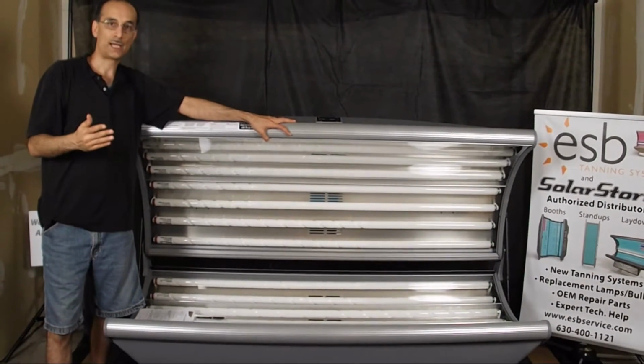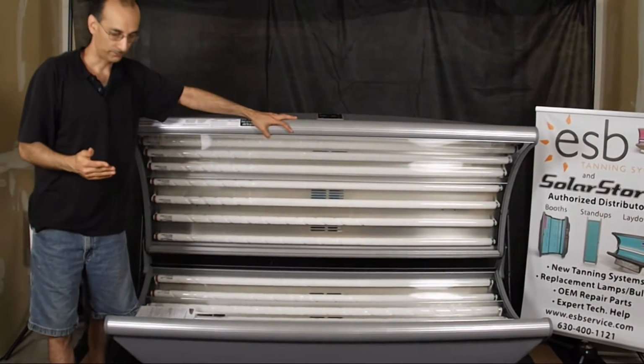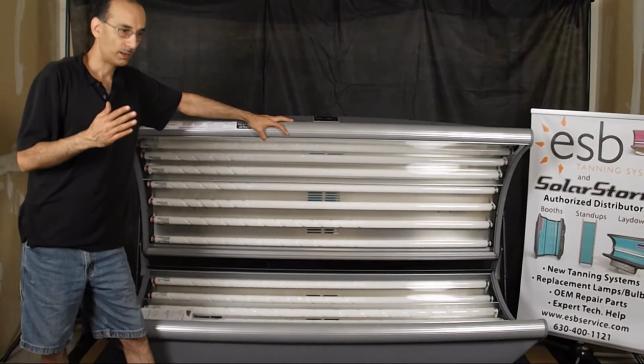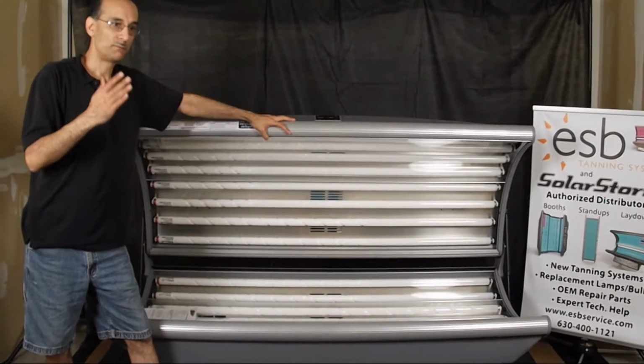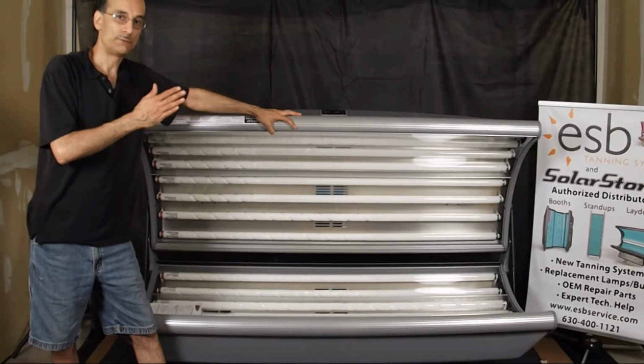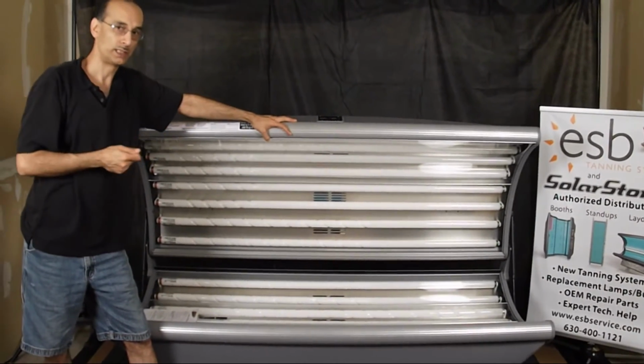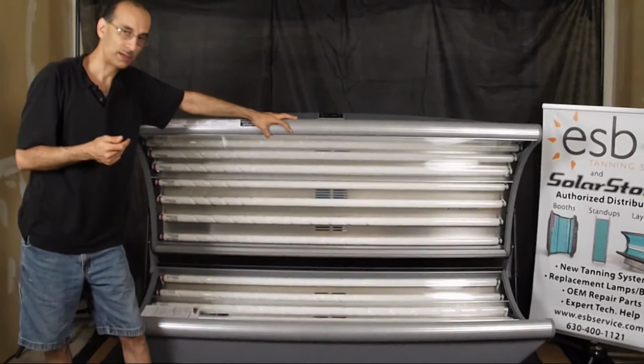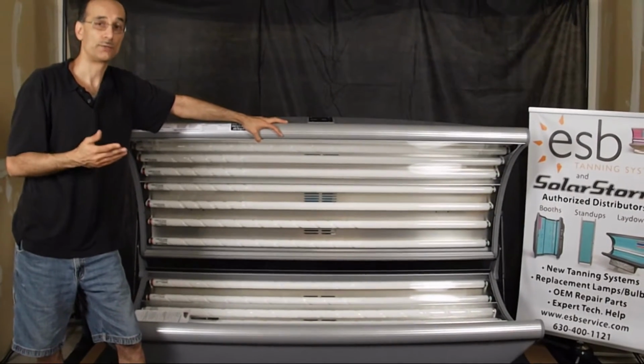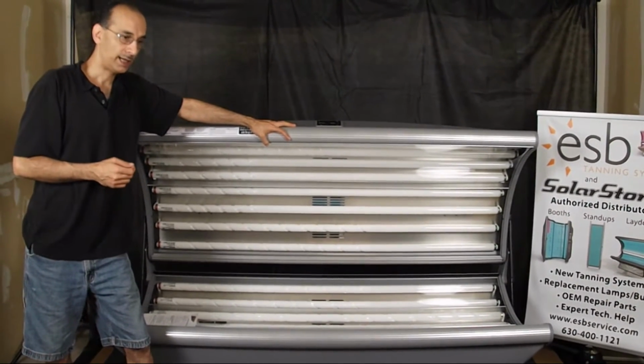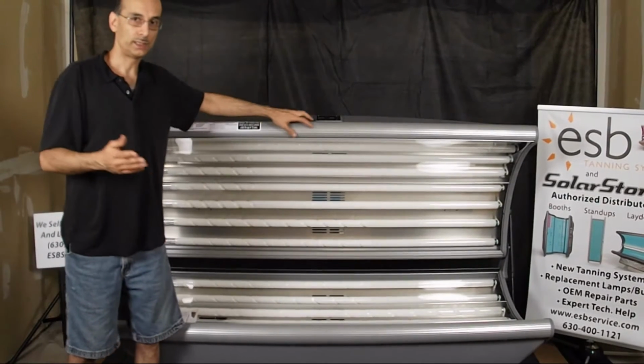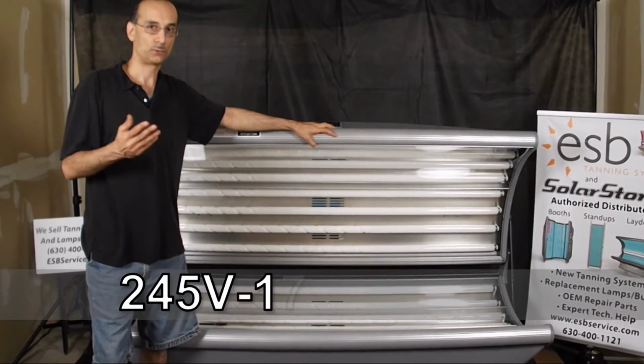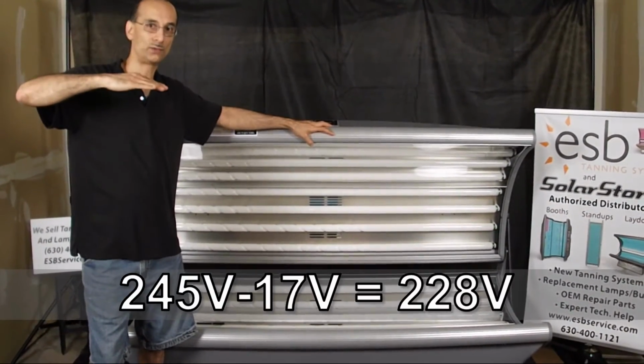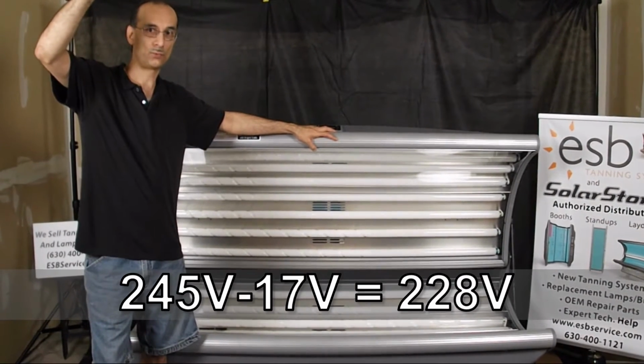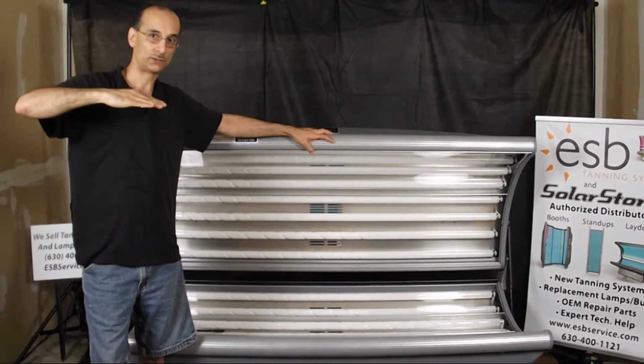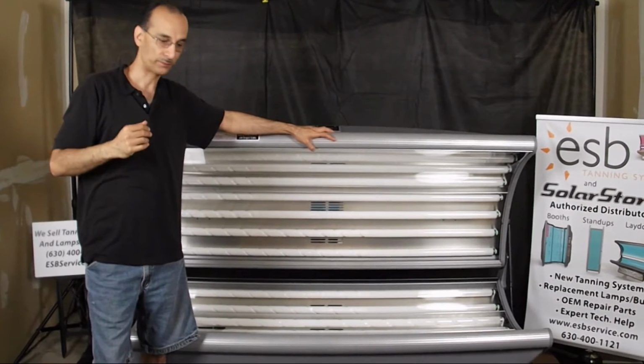Now, this is a lot more common on the 220 side because your voltage on 220, if you actually run a voltmeter on your receptacle, a lot of times you would find that your voltage is closer to 245 or 250, say. And this is where you would need the buck booster for sure to drop that receptacle voltage from about 240 down into the acceptable range for your tanning bed.